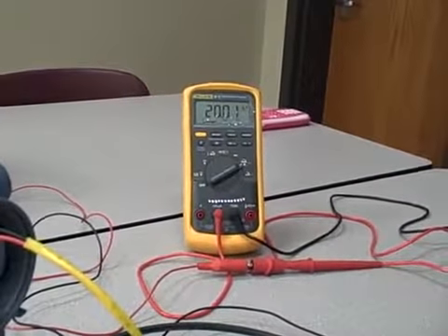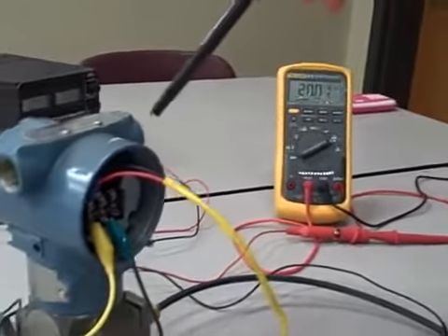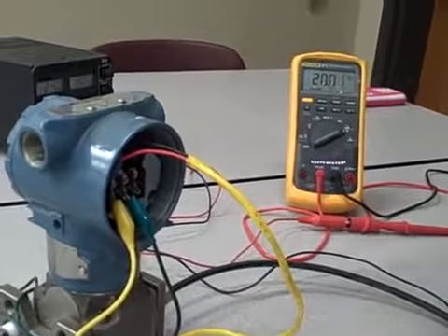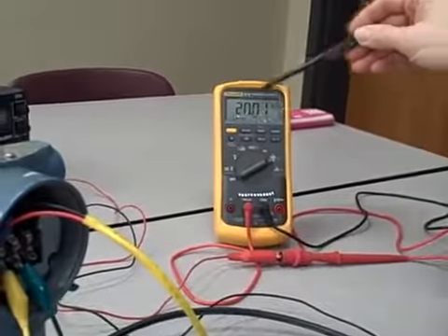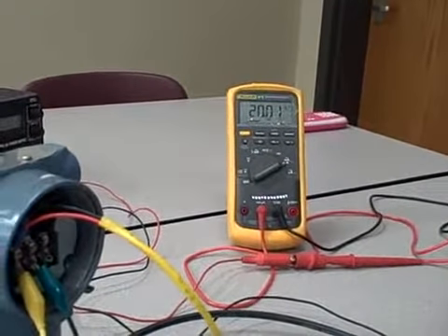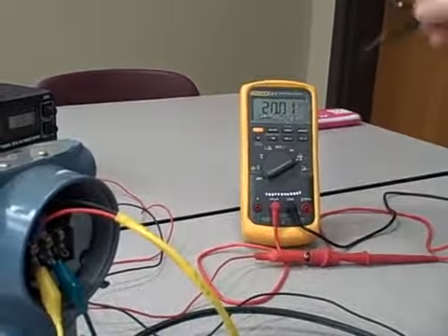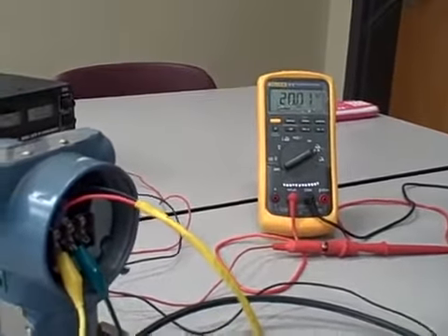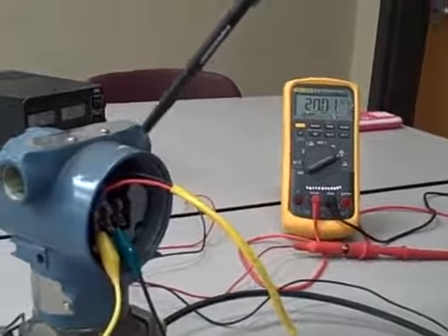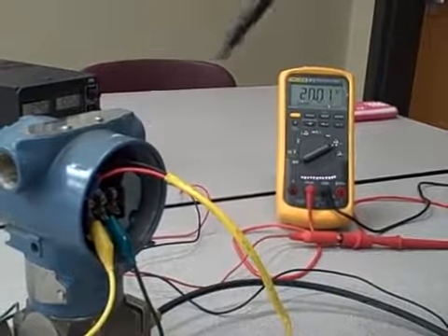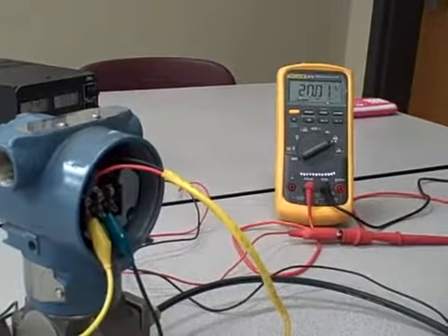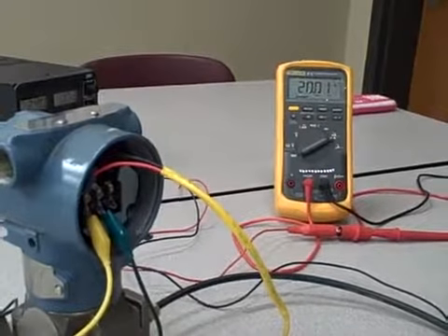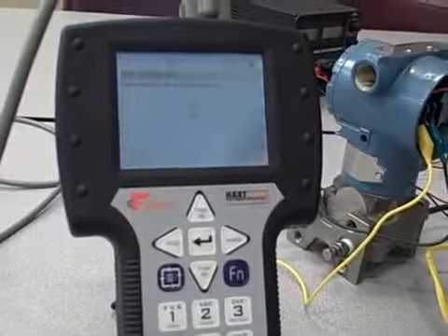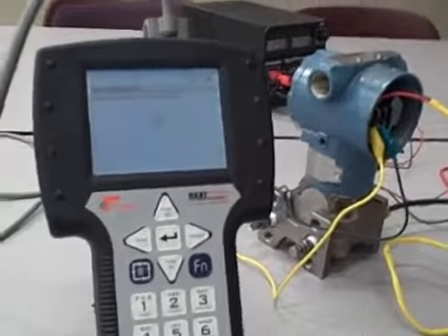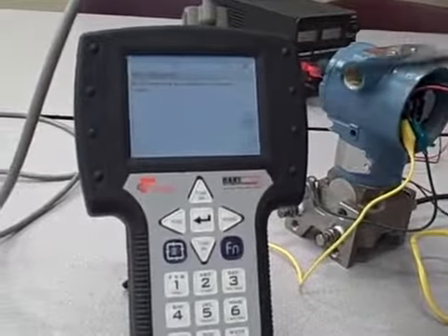Now, as far as this transmitter knows, it is actually outputting 20.00 milliamps. If we see a discrepancy such as this, 20.01, it may mean that our testing instrument is out of calibration, or it may mean that the transmitter is actually outputting a little bit more current than it thinks it is, in which case we can fix that with what's called a digital trim. Let's go back to this. We'll abort that test and explore some of the other menus.